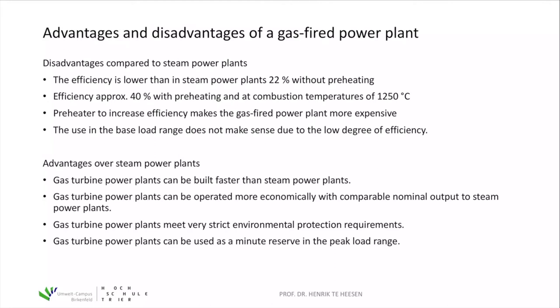On the other hand, advantages compared to steam power plants include: installation is rather fast since the system is not that complicated. Gas power plants can be operated economically at comparable output to steam power plants. Typically, gas power plants are mainly used for the peak load range. The key advantage is that gas turbines can produce electricity within seconds or even a minute at full power — a stark difference from steam power plants, which need at least minutes or even hours to increase their output.